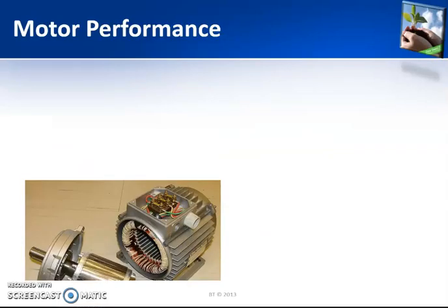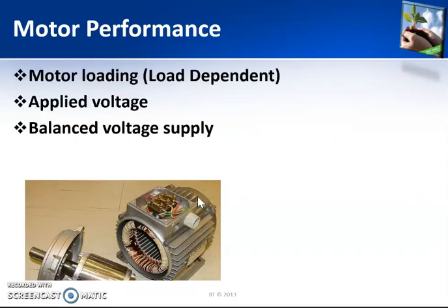So now we will be seeing the parameters related to the motor performance. The first one is the motor loading. Motor loading is an important parameter which is going to define the performance of the motor. Next one is the applied voltage, and the last one is the balanced voltage supply. Motor loading we will be seeing in depth in the future slides.